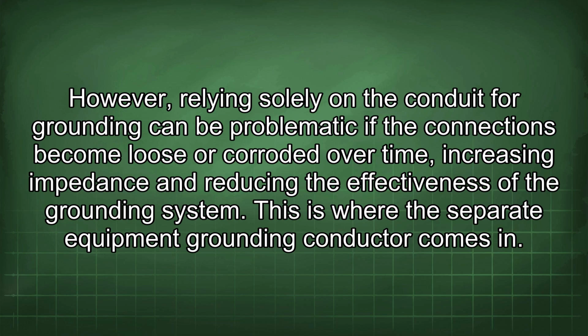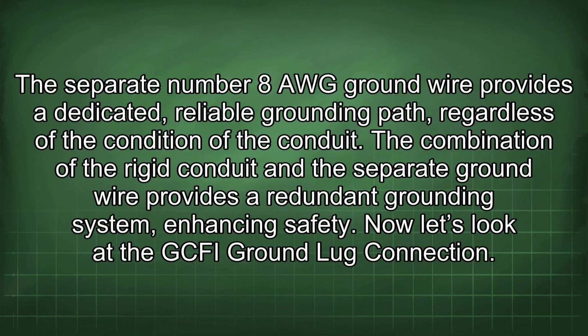This is where the separate equipment grounding conductor comes in. The separate number 8 AWG ground wire provides a dedicated, reliable grounding path, regardless of the condition of the conduit. The combination of the rigid conduit and the separate ground wire provides a redundant grounding system, enhancing safety.